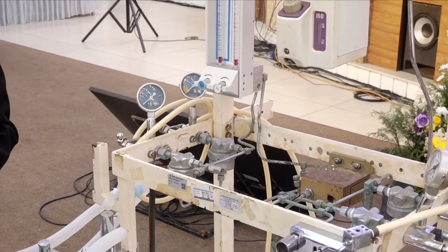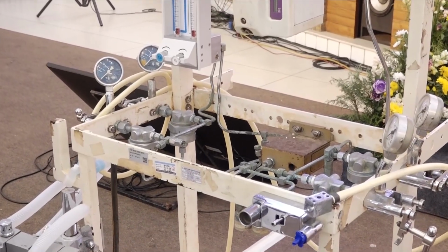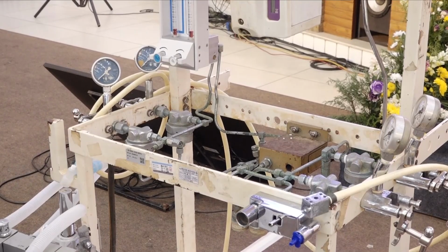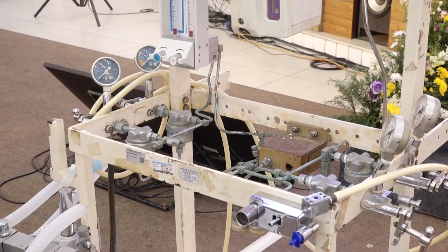So we have 3 systems based on the amount of pressure inside. The high pressure system is basically the cylinder pressures. The cylinder pressure of oxygen is 2000 pounds per square inch. The cylinder pressure of nitrous oxide is 750 pounds per square inch, and till the last drop of nitrous oxide is there, it will show only 750 pounds per square inch. It is the vapor pressure of nitrous oxide at 20 degrees centigrade, because nitrous oxide remains a liquid at room temperature because of its critical temperature.